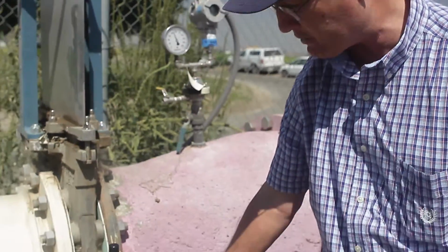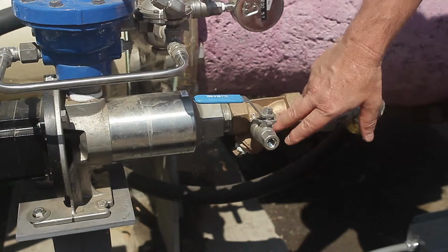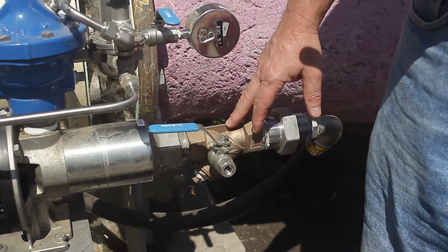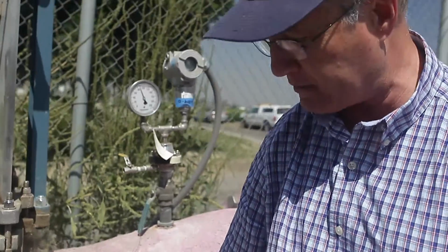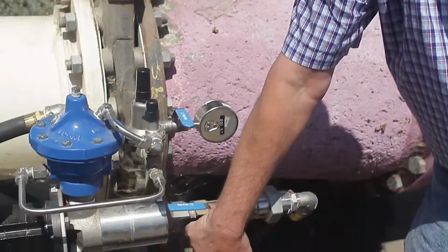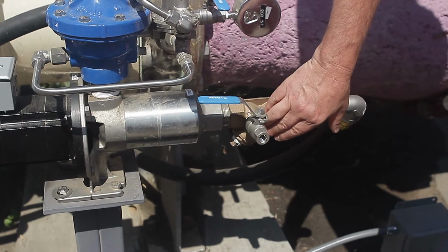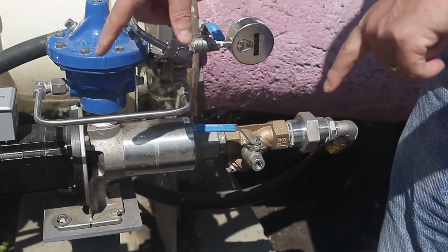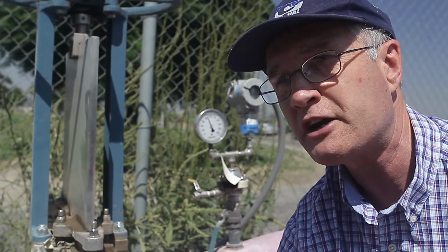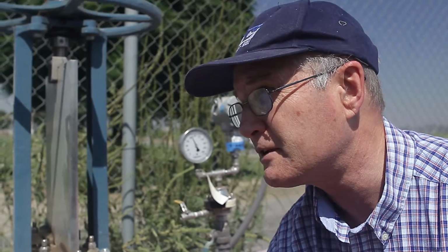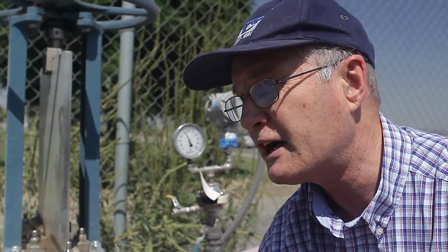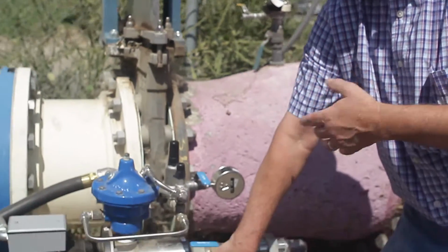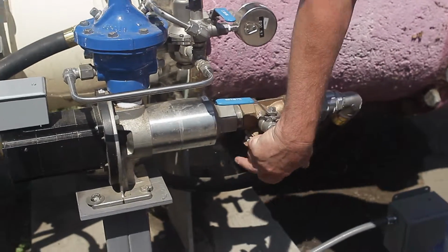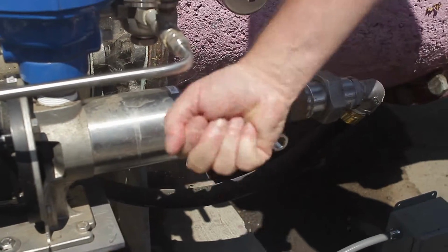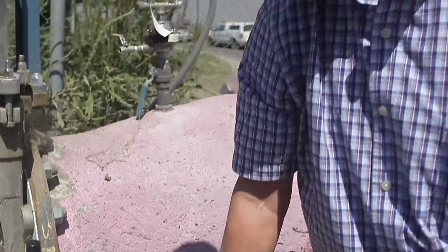The generator is generating. The important thing to understand is the filter. I'm not that familiar with water quality. I understand it's reclaimed. It should be relatively clean, but periodically they should probably flush the filter here, because if this gets clogged, your output from your generator will decrease. So that's something probably a good idea to monitor, maybe even within 2 weeks, just to see how quickly it's clogging. Thereafter, you can judge the frequency and then maybe even introduce a blow-down valve to manually just flush it. Would be a good idea. So that's the key thing, is monitor this filter.